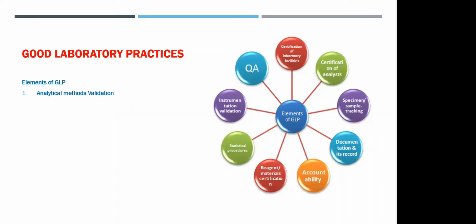So you have to have analytical method validation: whatever method you are using to test the product has to be validated. Equipment: validated, calibrated. If calibration is required every day, then you are actually calibrating it every day. If the calibration frequency is once a week or once a month, you are actually following it. This is always defined by the manufacturer or seller of the equipment, or in the equipment manual, where we find out how sensitive the measurement is, how sensitive the equipment is, and how frequently the calibration should be carried out.